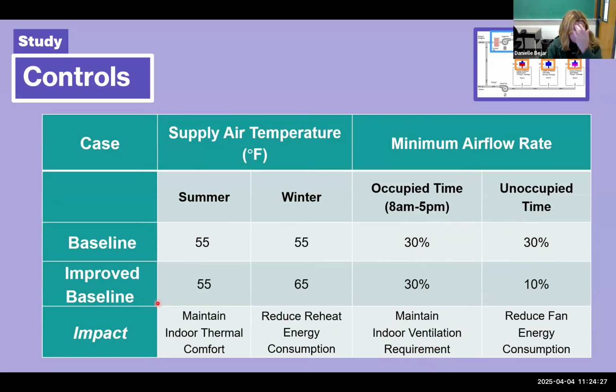Then for our improved case, during the winter time, we're going to increase that supply air temperature to 65 degrees Fahrenheit. So remember, this is the supply air temperature after the air handling unit. So the increase in supply air temperature will decrease the reheat energy consumption because now it's 65 degrees Fahrenheit. The air doesn't have to be heated up as much. Then for the minimum airflow rate, we have during occupied time, so this is working hours, 8 a.m. to 5 p.m. There's people in your space. You want to make sure that the airflow rate is still 30%. But during unoccupied time, there's no one in the building, so it's outside of working hours. We can reduce that flow rate to 10%. And so then this will reduce the fan energy consumption because remember that the fan is responsible for moving the air. And so we're decreasing that minimum airflow rate. So those are our two cases that we're running.